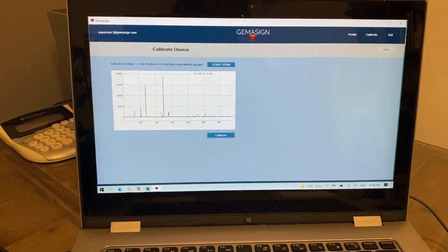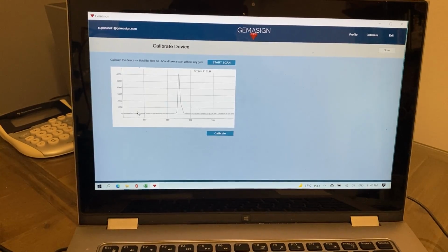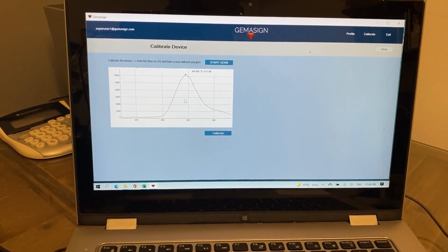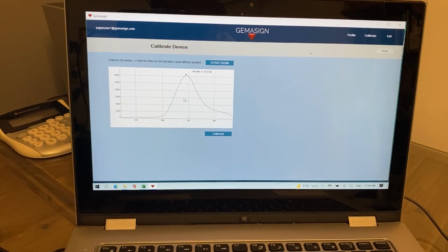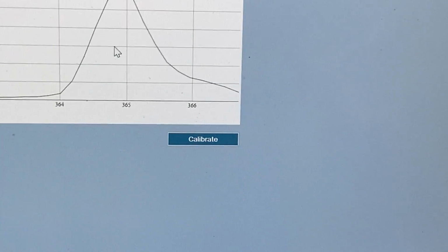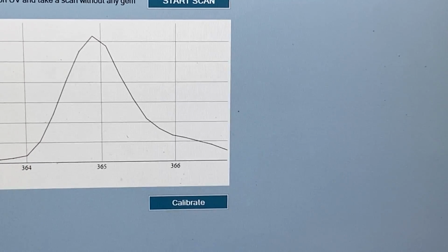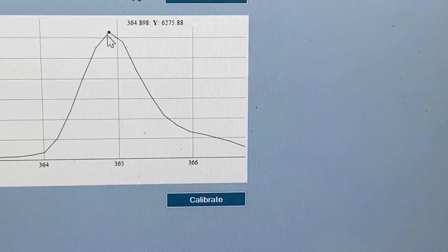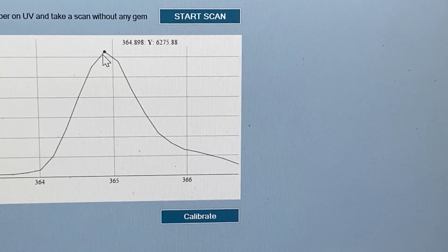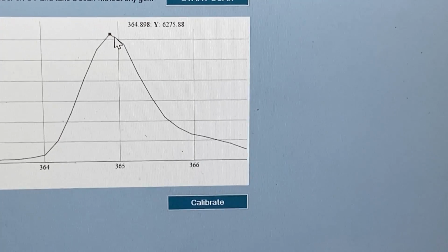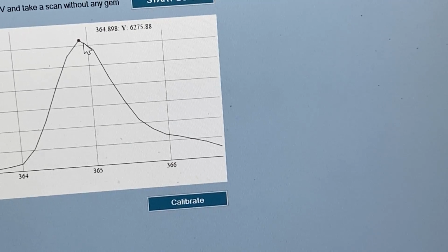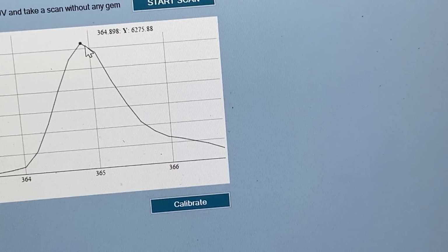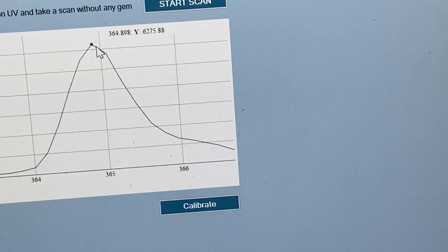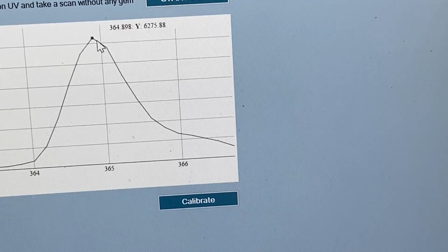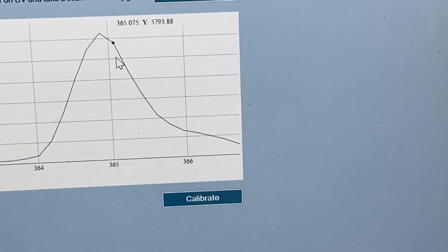Now, I can check and see how this calibration came out. Let's say I take this peak right here, and I blow it up, so I know just exactly where the peak is. Now, the peak you can see, if I blow it up here, there we go. Okay, let's move this back. 364.89 is the peak, and I can tell you that peak is supposed to come out at 365.01. So you can see that's coming out about 1 to 2/10 of a nanometer off of the absolute perfect value.